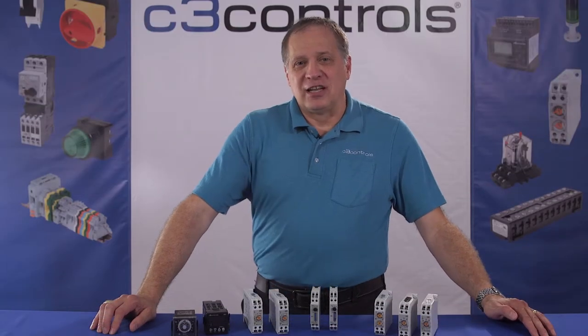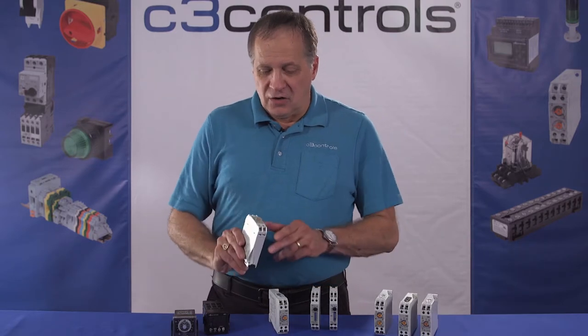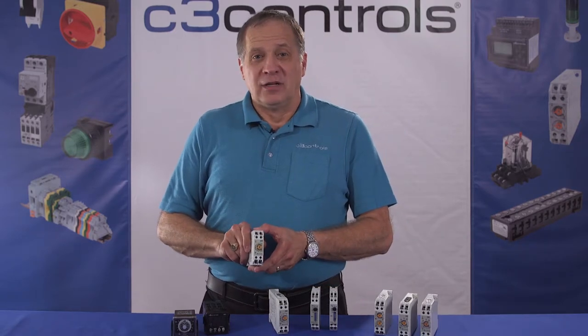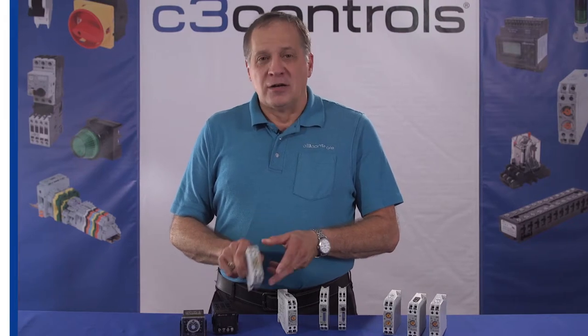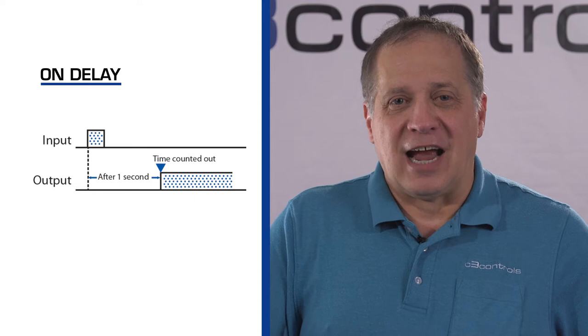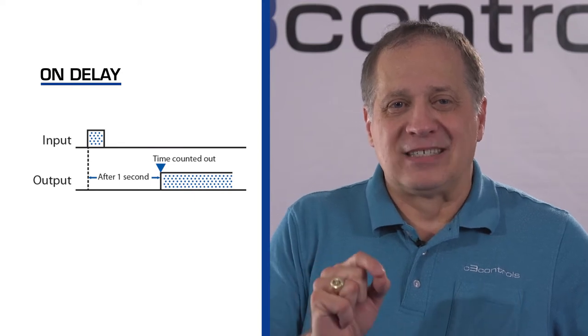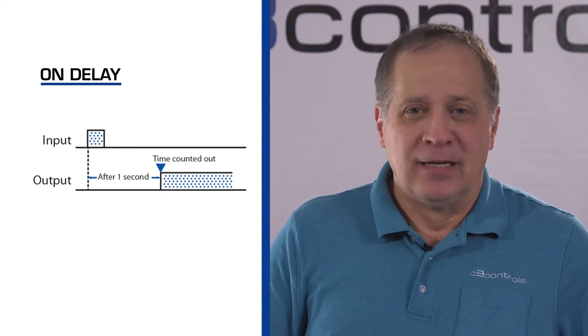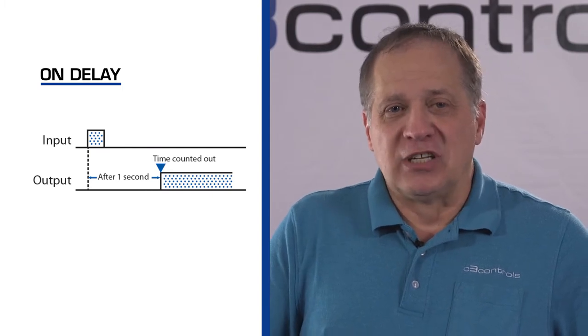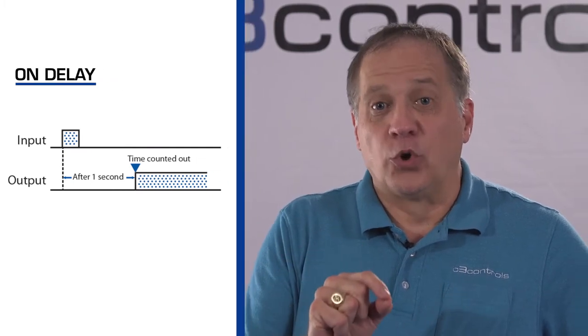Let's talk about the functions on the relay. There are a number of functions that can be selected using the function selector on the electronic timing relay. One of them is on delay. With on delay operation, the timer receives an input and then the output signal is sent by switching the timer contacts after a set time delay. This name is used because there is a delay between when the input signal is received, or turns on, and when the output signal is actuated. On delay operation is the operating mode most often used for automated machines.